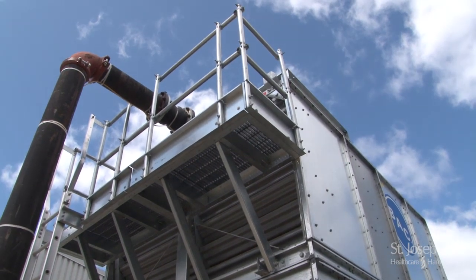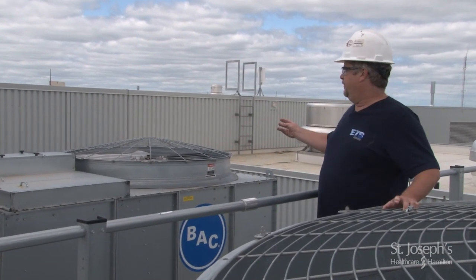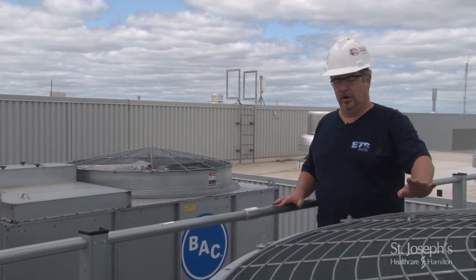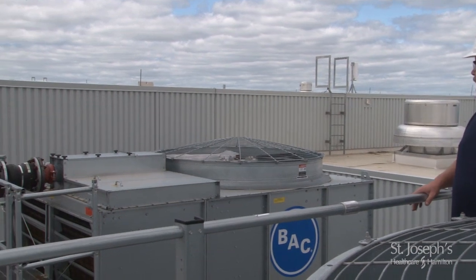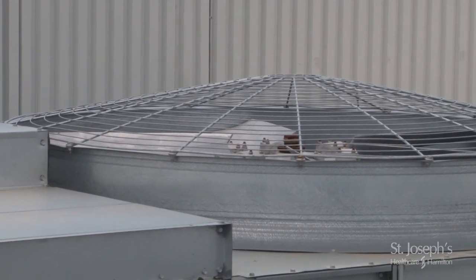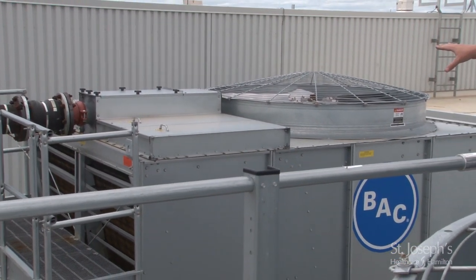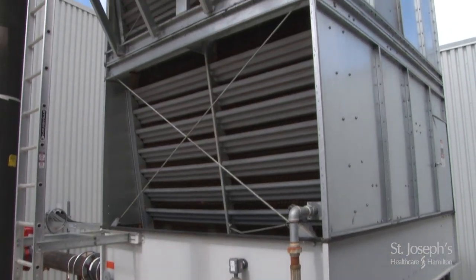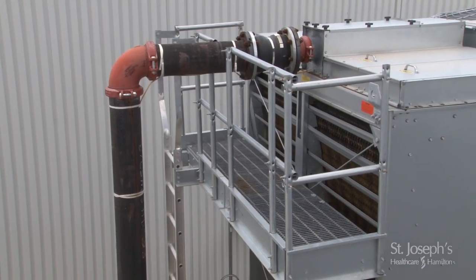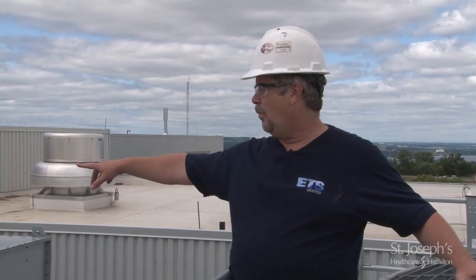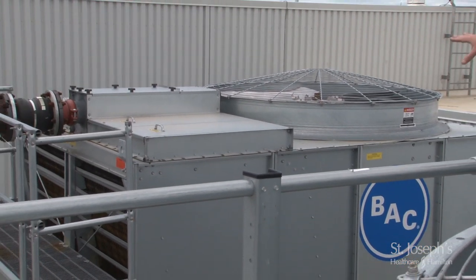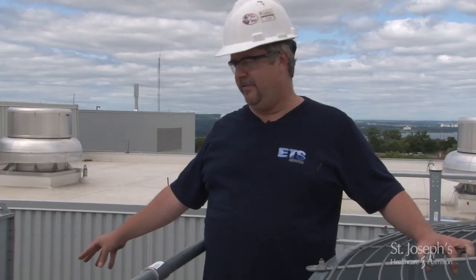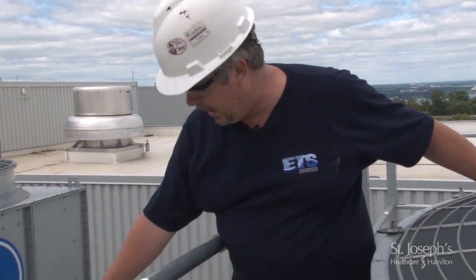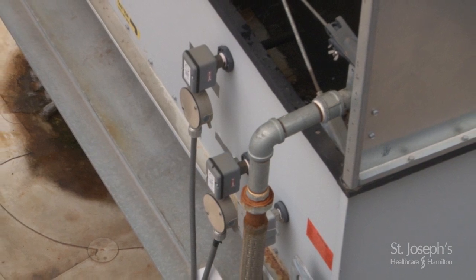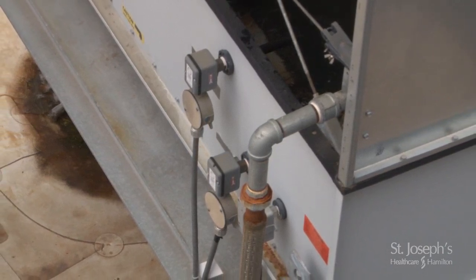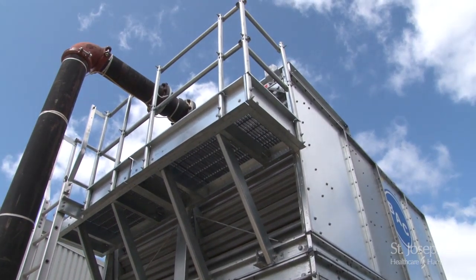Over to my right, you're going to see the Series 1500 cooling tower. Basically, this 1500 series cooling tower is the baby brother of the Series 3000 we've been talking about up to this point. There is not a lot of difference between this tower and that one, other than it has a smaller fan. It only draws air through one side of the cooling tower. It all looks the same, just on a smaller scale than the Series 3000. It also has a hot water box basin on the top, just like this cooling tower does. We have our fan assembly, which is also set for winter operation. Down to the side, you're going to see that you've got your makeup valve, your high alarm, cutout switches, and thermostats. It's all the same, and the maintenance is done exactly the same on that tower as you would on these 3000 series towers.